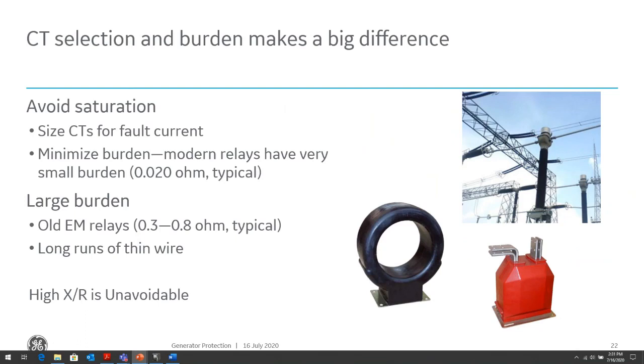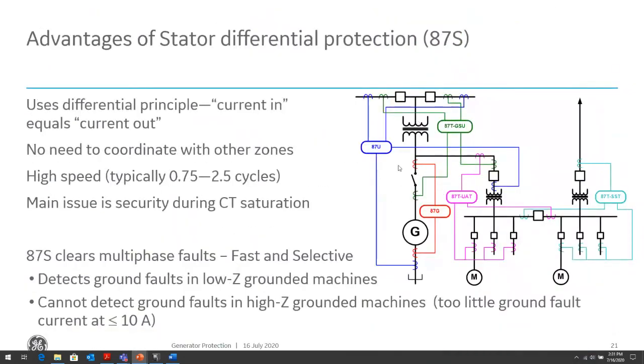So what is CT saturation? What's the phenomenon of CT saturation? What does the relay see? Basically, the relay sees currents that are not reflective of the primary currents flowing in the system. So in our generator example, if we have saturation in the terminal CT, we're not going to see the primary currents that are flowing in that system.